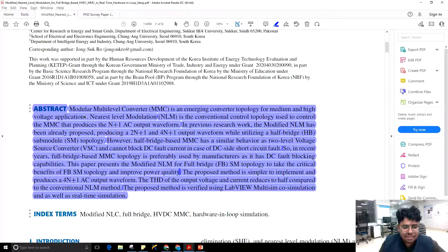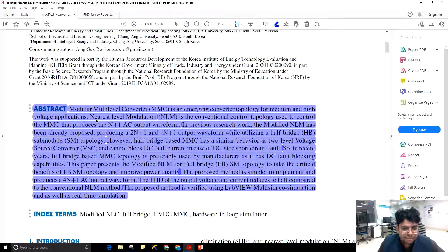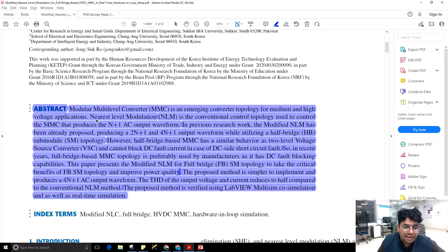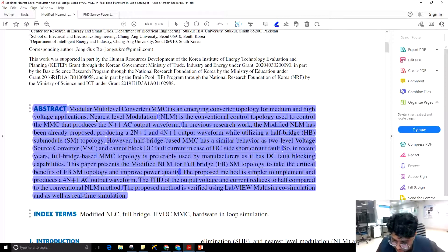Combining smaller submodules to make a larger system is known as modularity. In MMC, hundreds of cells can be cascaded to get more number of levels — hundreds of levels — and this feature is known as modularity. Other than modularity, MMC also offers salient features such as reduced dV/dt stress, reduced dI/dt stress, fault blocking capacity, and lower switching frequency. Without a filter at the load side, the output voltage and current have better power quality, so it has improved power quality.